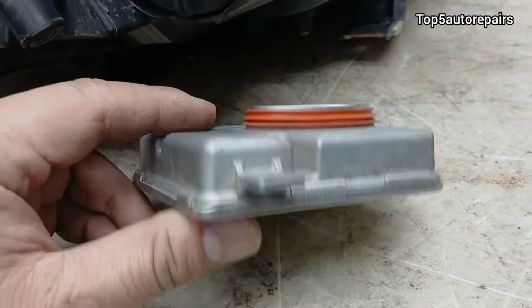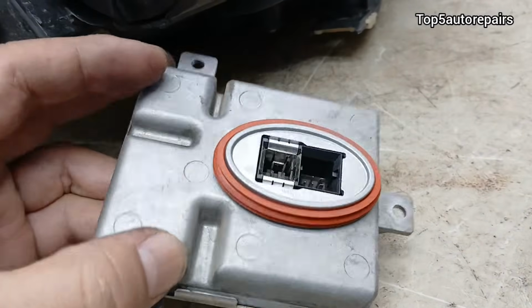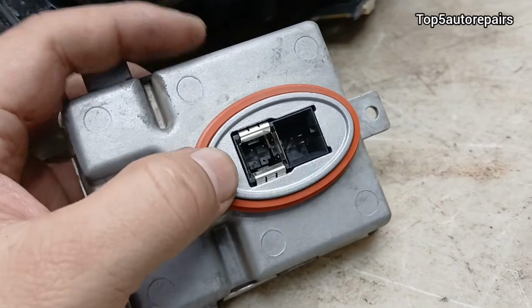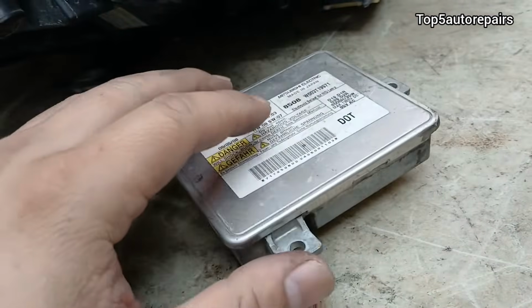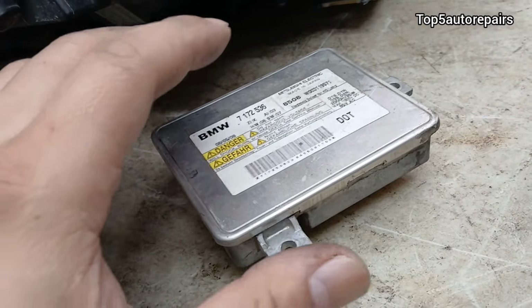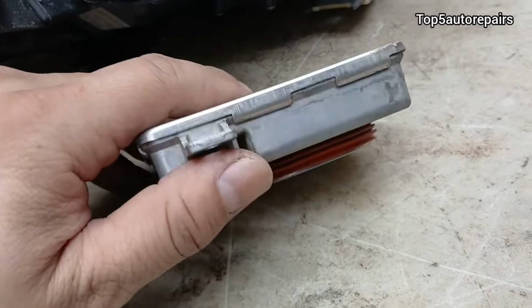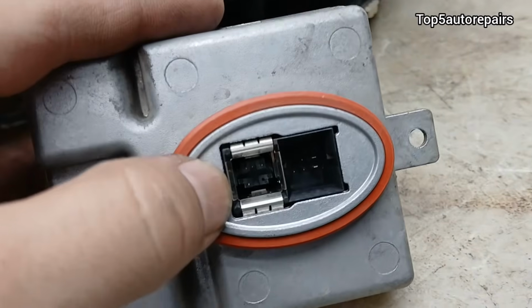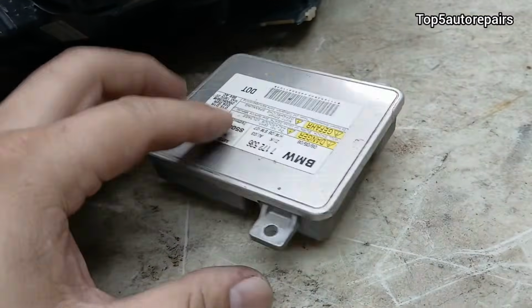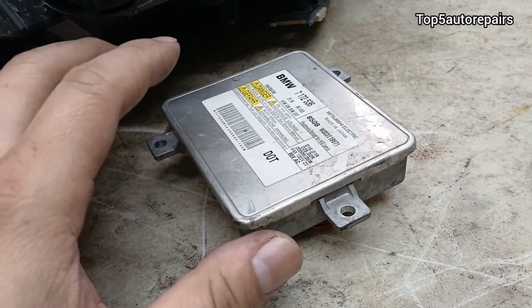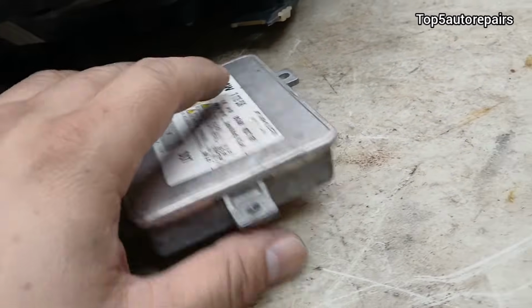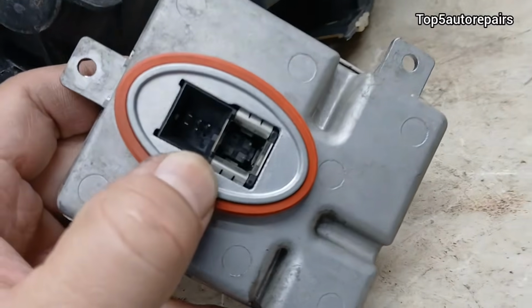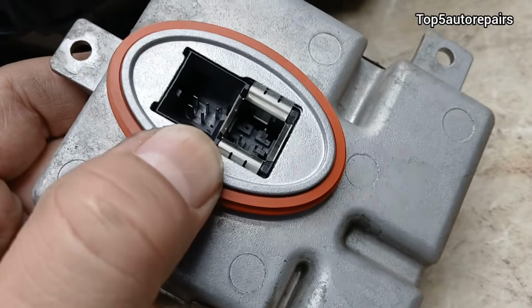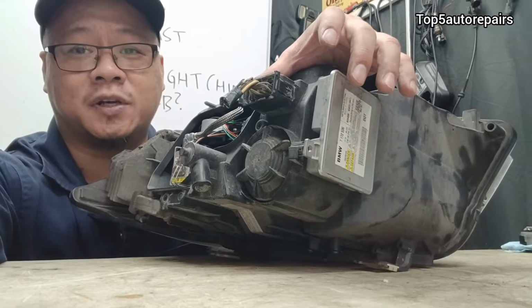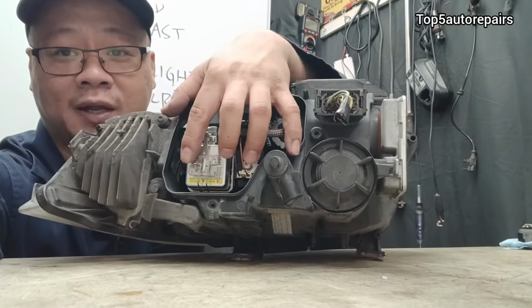Well, the first thing you want to look for is burn marks on the ballast. Again, it is a transformer and it provides high voltage, and when this part fails, you can see burn marks on the connection or on the case. Of course, you don't always see that, but that's one of the first things I'd probably check if the ballast had failed.